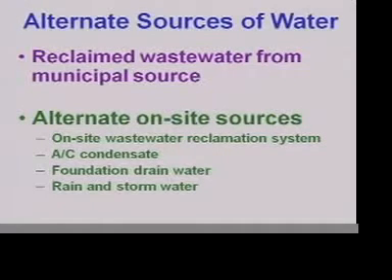The other things that we can do is look for alternate sources of water. We've talked about reclaimed water. Alternate on-site sources are becoming more and more popular. We're going to have a lot of talks about gray water, but you have air conditioning condensate, foundation drain water — all types of things that can be used in your cooling towers. University of Texas at Austin collects AC condensate, foundation drain water, a little rainwater, and a couple other things, and gets 130,000 gallons of water a day out of the system.